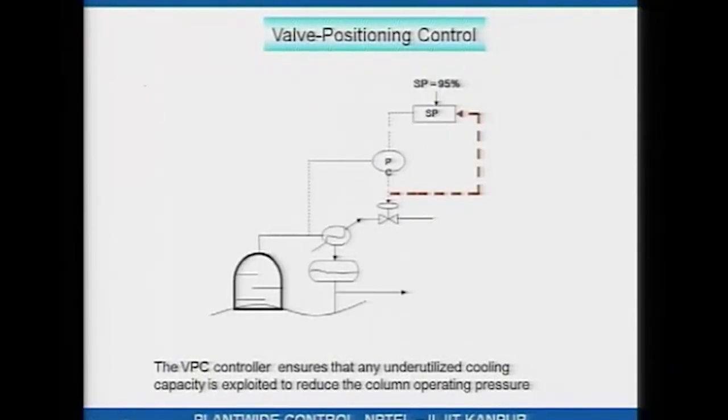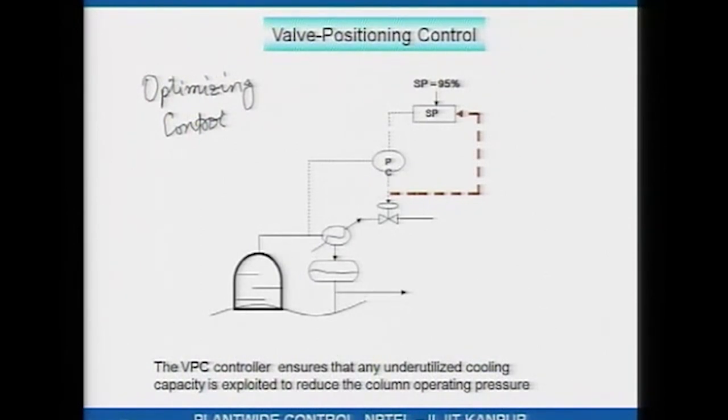This is another example of a valve positioning controller application. It is for this reason that valve positioning control is also sometimes referred to as optimizing control — by implementing valve positioning controllers, you are trying to either minimize steam consumption, minimize electricity consumption, or in another application maximize production or throughput. Valve positioning control is routinely employed in order to make your operation as economical as possible.